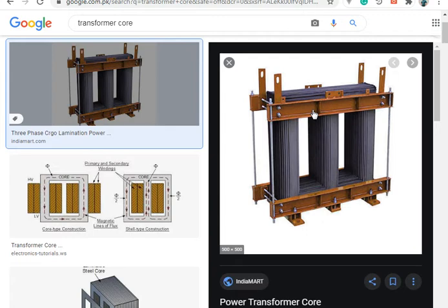One thing very important, which I will discuss most probably near the midterm: every transformer or winding working at 50 Hertz, a low frequency transformer, is always under the effect of some motional force on the winding. Have you ever seen a transformer that has blown out, its windings gone? You will witness that the transformer's windings either squeeze inward when it is short circuited, or they blow outward, taking the tank also with them.